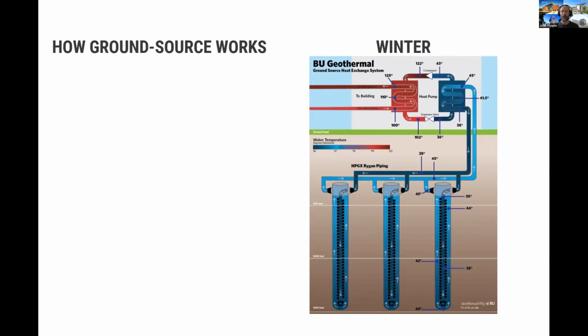In wintertime, we simply reverse the process, and those heat pump chillers are now rejecting heat into the building and pulling it out of the ground. We have to manage all those temperatures to keep the water from freezing, particularly because you cannot put glycol into a borehole that isn't fully grouted, and you cannot physically fully grout a 1,500 foot deep borehole. So it's just water in that ground loop.